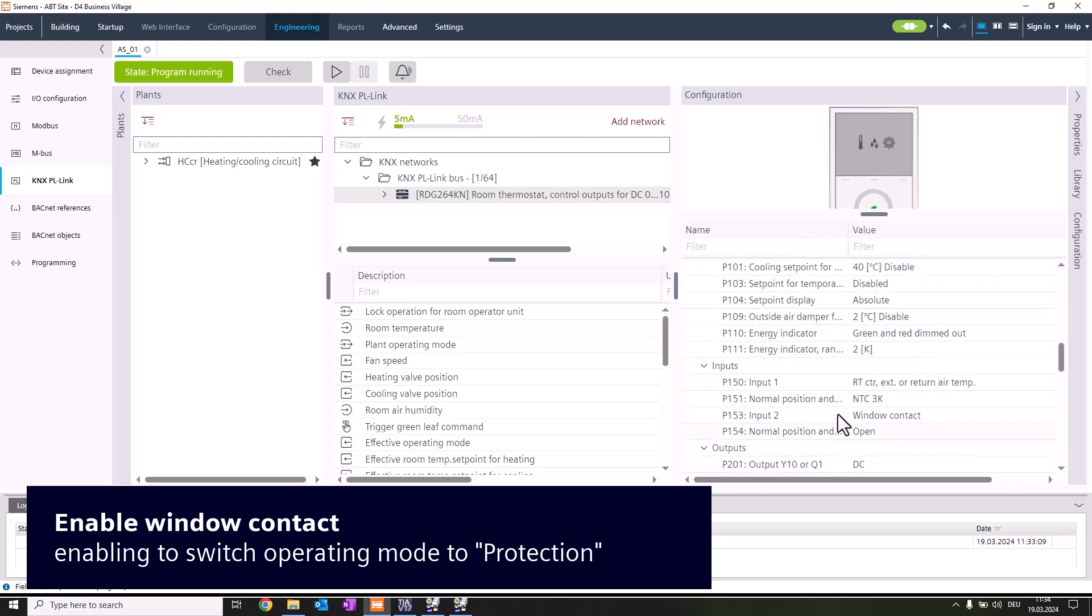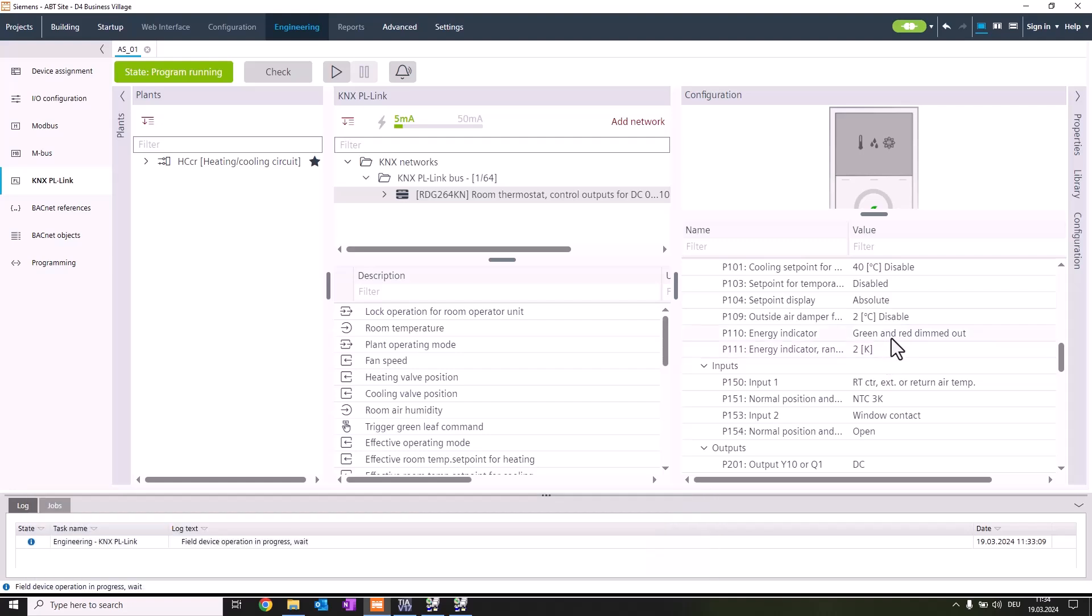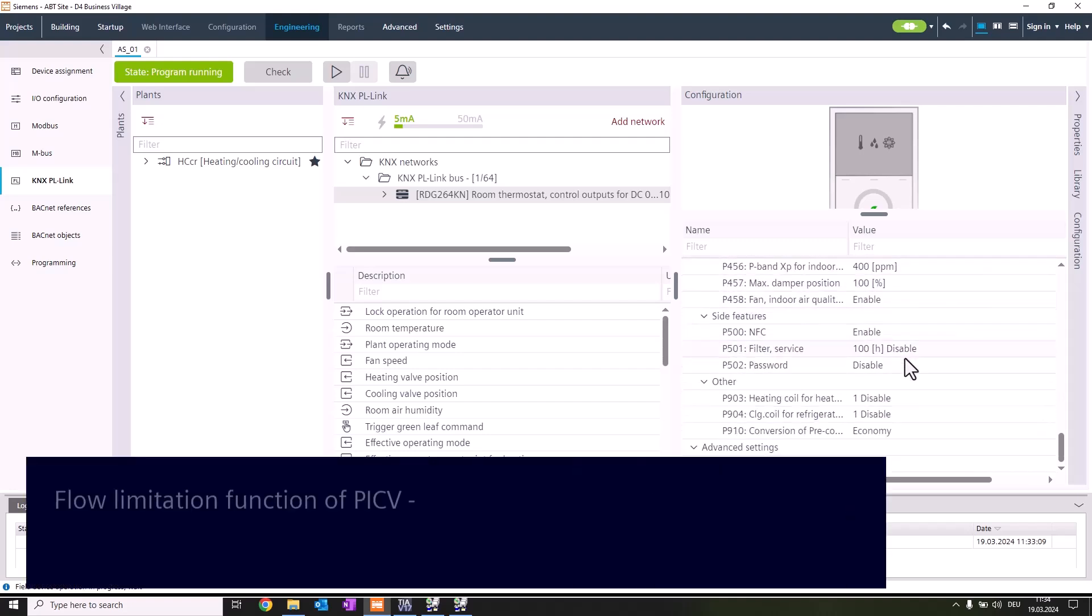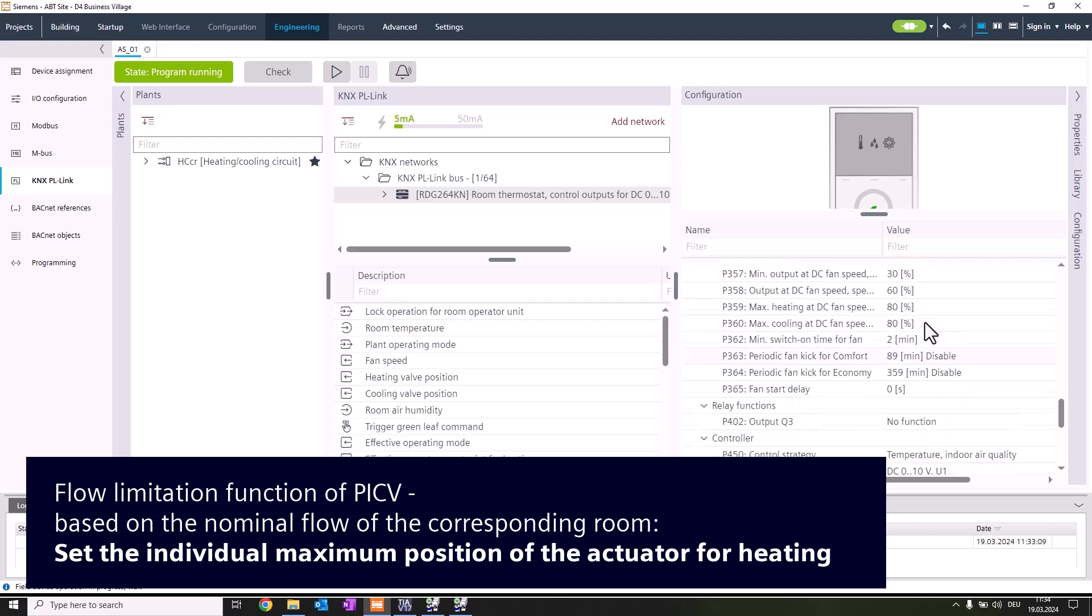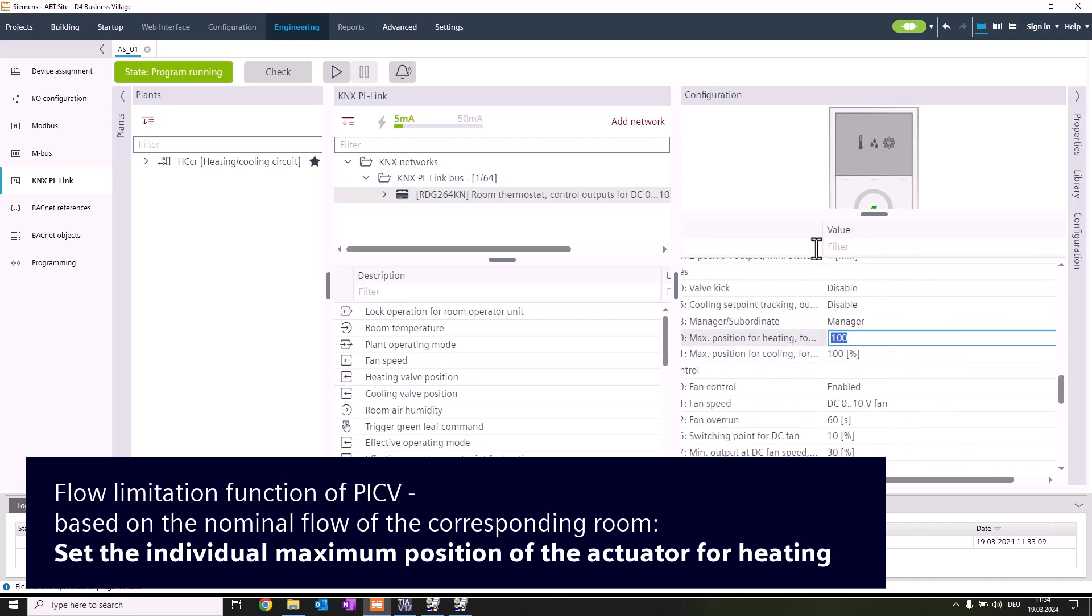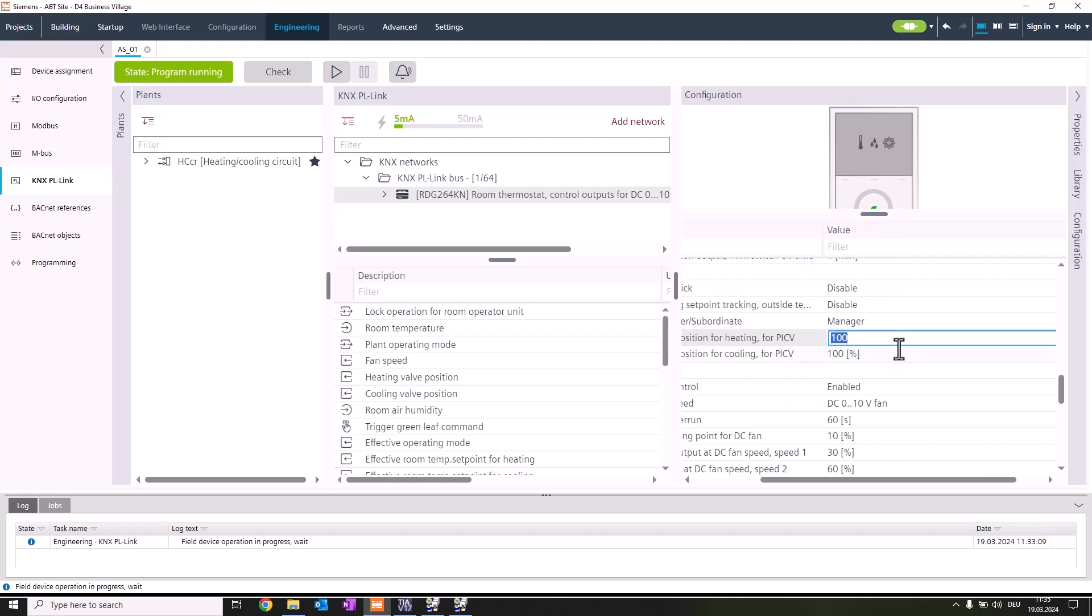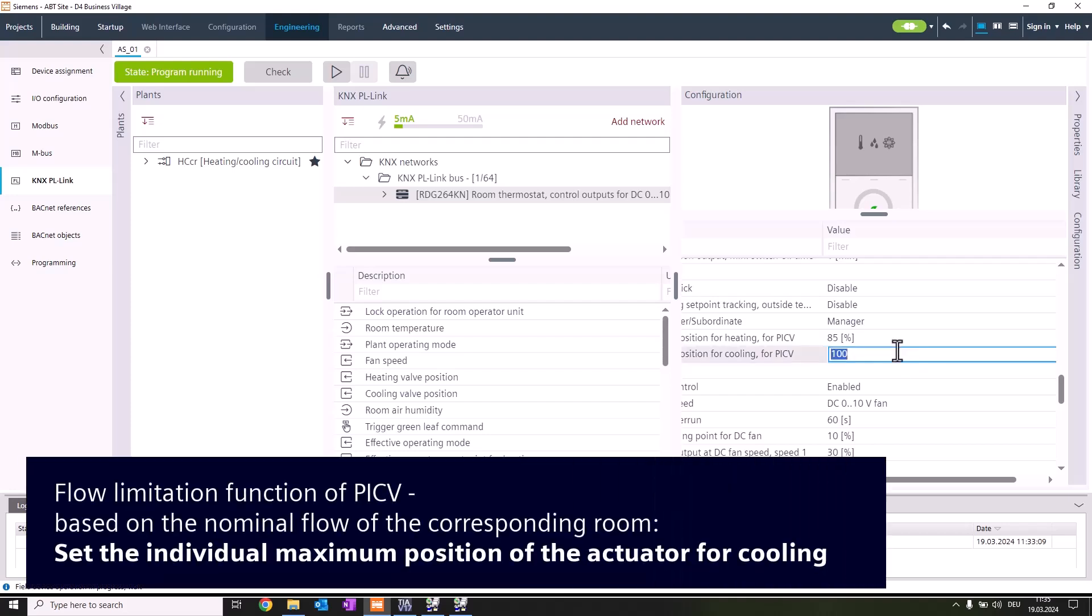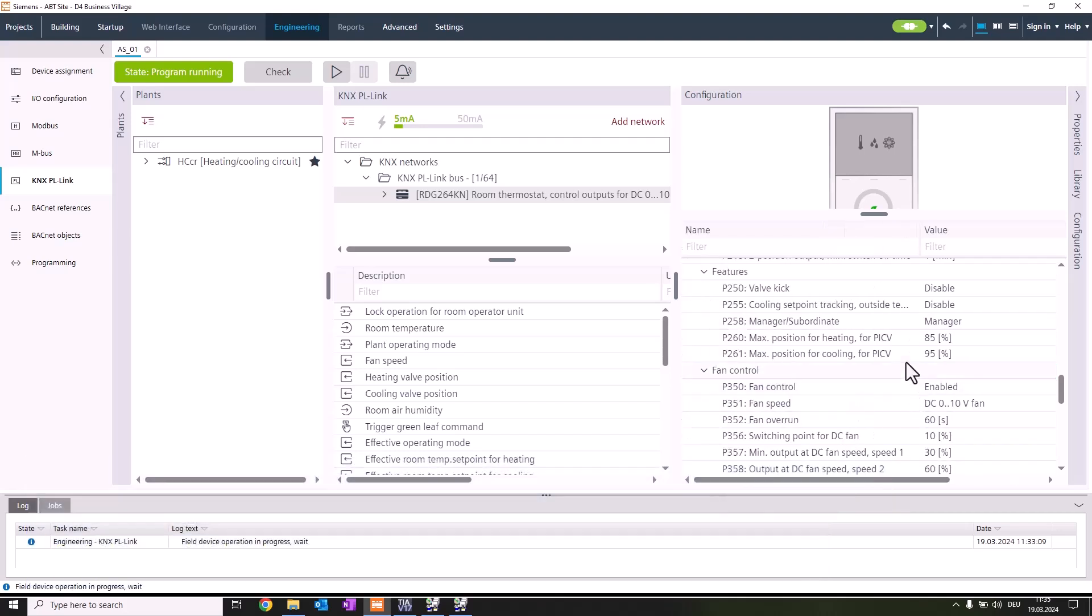As a last step, because it's a PICV application, we're also going to adapt the max position for heating for the PICV for the nominal airflow to make sure we have no hydraulic problems. We take 85 percent for heating and 95 percent for the cooling sequence. This is according to project specification. Now the application is configured and next we're going to the programming part.